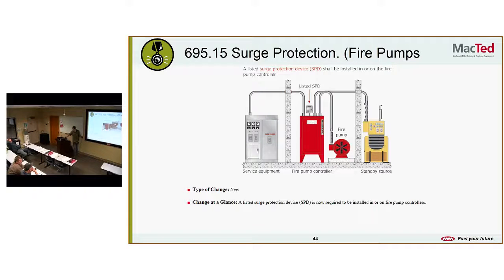Surge protection, fire pumps. A listed surge protection device, SPD, is now required to be installed in or on fire pump controllers. This seems to be a common theme, these surge protection devices. I don't know if they're becoming more accessible or they're better than they used to be, but it seems like they're popping up now all over the place. So if you're installing anything important, put a surge protection device on it.